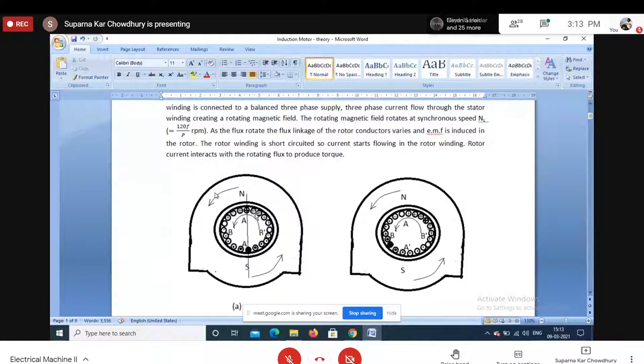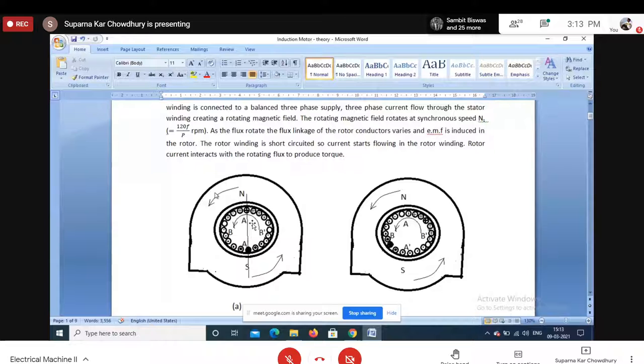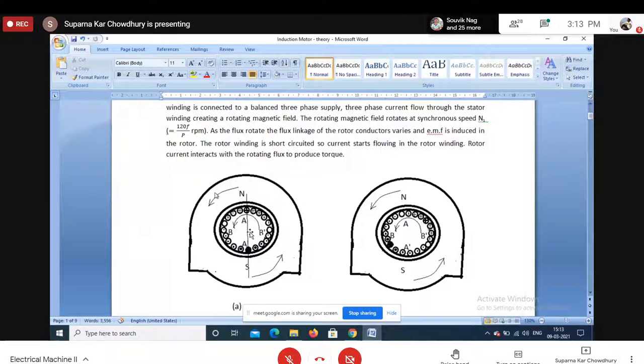All conductors carrying current interact with the flux to produce torque in the same direction, resulting in a net torque that rotates the rotor in the direction of the rotating magnetic field. This reduces the speed difference between the rotating field and the rotor conductors. The rotor tries to catch up with the synchronous speed, but can never reach it — at synchronous speed, the rate of change of flux is zero, so no EMF and no torque would be produced.